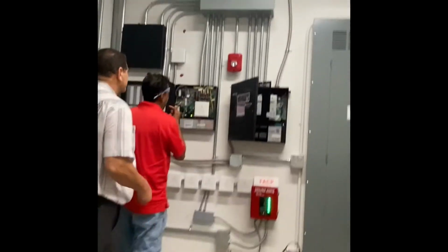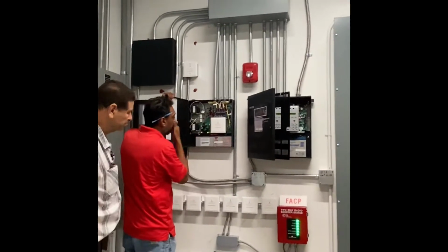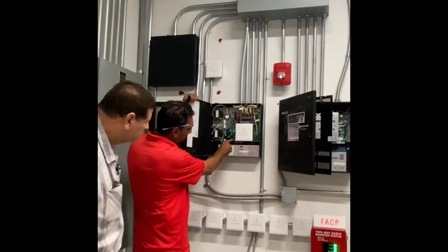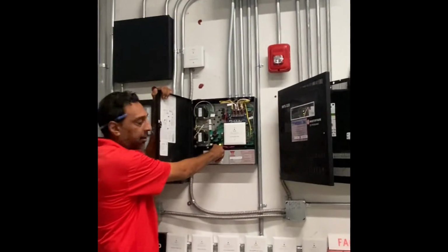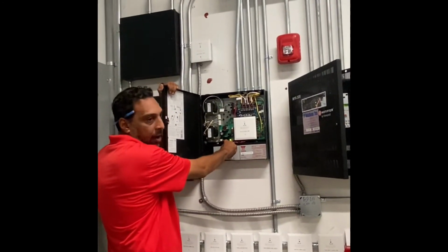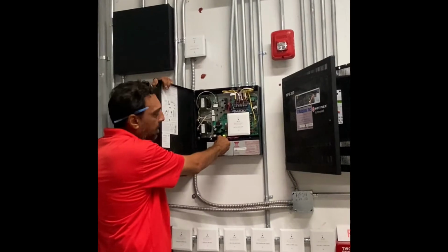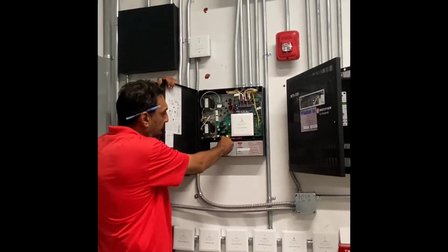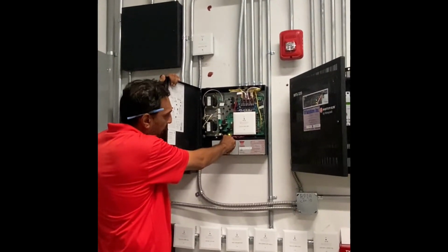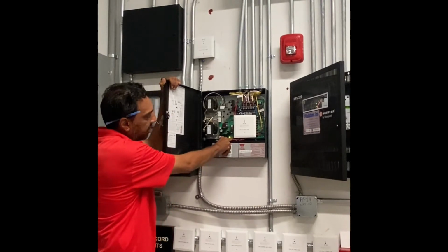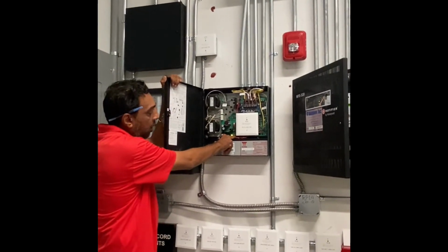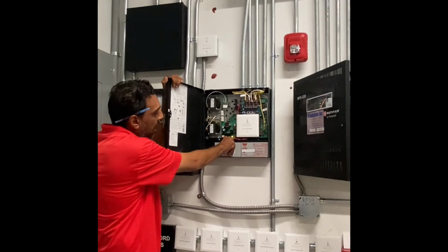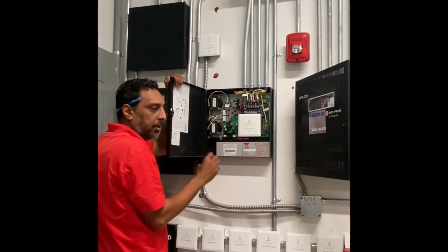All right, so this is your power supply here for your strobe circuit, okay? So if you get a battery trouble, that battery light will come on. Okay. If you get a ground fault, maybe a wire's nicked or something happened or maybe something got wet, this ground fault light will come on. If you have an AC fail, that will come on. Or if the charger's acting up, that will come on. And this NAC trouble, it'll blink.